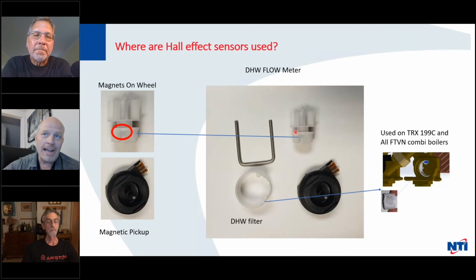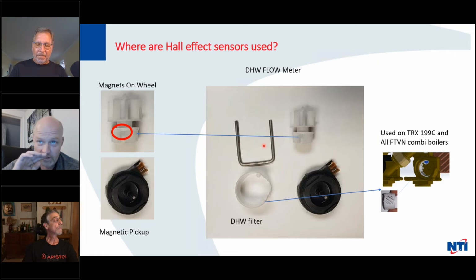who's gone through and done the math and said, well, each of these vanes carries 2 milliliters of water or 2 ounces of water. Based on how many times it spins per second, we can determine how many gallons per minute are flowing to the fixture. The other pieces you see in the photo here, this little horseshoe-shaped clip is what holds this whole assembly into the boiler. So if you have not had to disassemble one, off on the right here, you can see the housing. So the brass housing is literally just a housing.